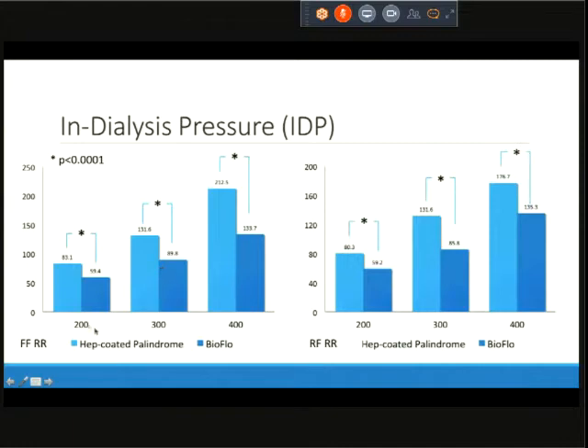Again, there are two different sets of data. The first one on the left is the forward flow, and the second one is the reverse flow. And as you can compare again between the palindrome versus the BioFlo, you can see a significant difference in all three flow rates, 200, 300, 400, that the BioFlo has the superior in-dialysis pressure. Again, the lower the in-dialysis pressure is, the better, compared to the higher one, as you can see here. And in all categories, both forward and reverse, the BioFlo shows superiority.